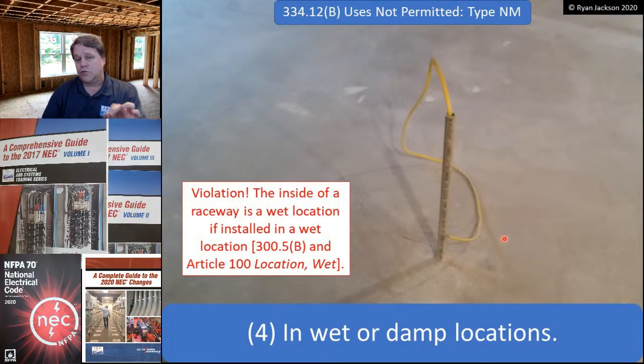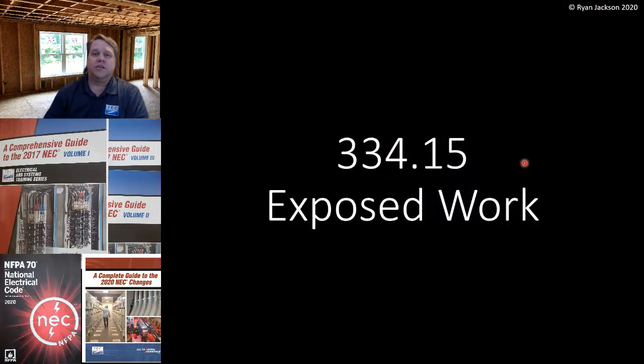Well, underground is a wet location. Even the inside of the raceway underground is a wet location. If you're like, oh wait, it wasn't underground, it was in the slab, well, if the slab is touching dirt, it counts. That's information you'll find in Article 100 under the definition of wet location, and also in 300.5(B). So this is a violation. We can't pull NM cable through that raceway because the inside of that raceway is a wet location. The same thing could be said for above-ground outdoor applications. If this conduit was above-ground outdoors, that too is a wet location. 300.9 is your code section for that.